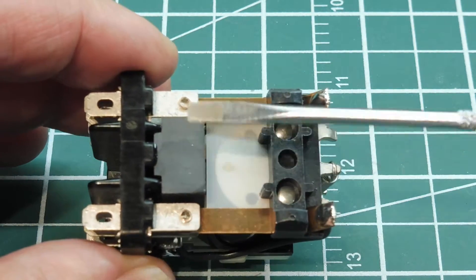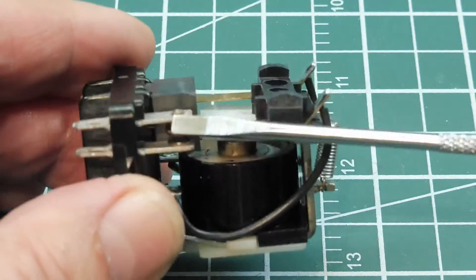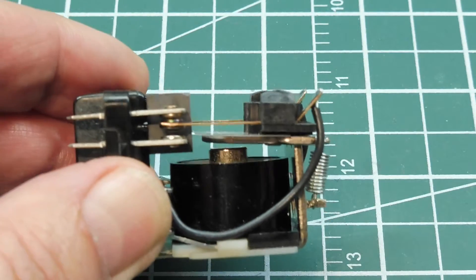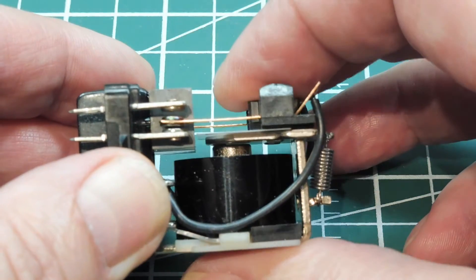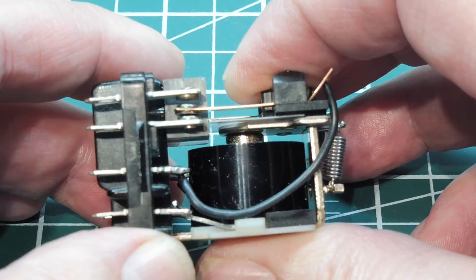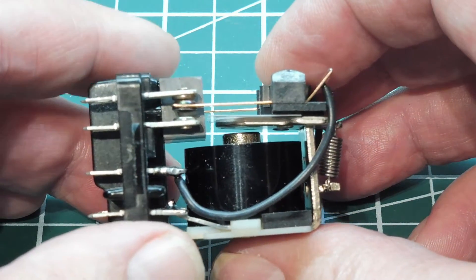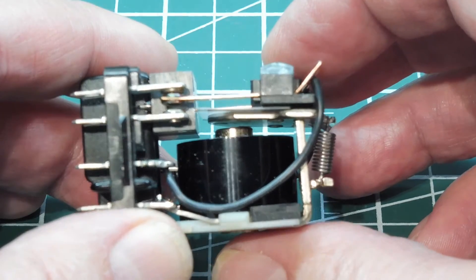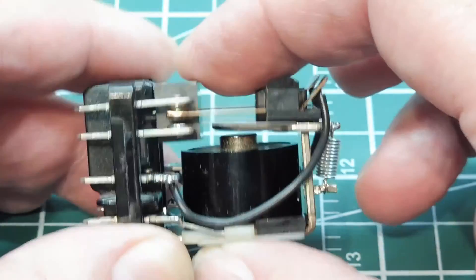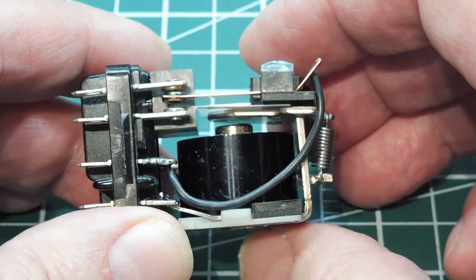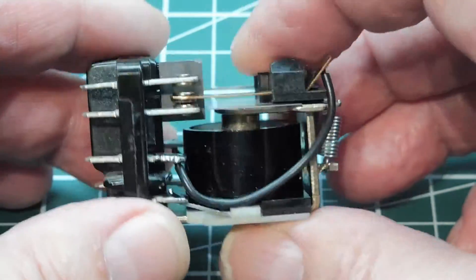And you can see it's very close to the contacts. So when you energize an inductive load, and then de-energize it, and you get that spark, the plasma will respond to the magnetic field of this magnet, and will actually blow out the spark.